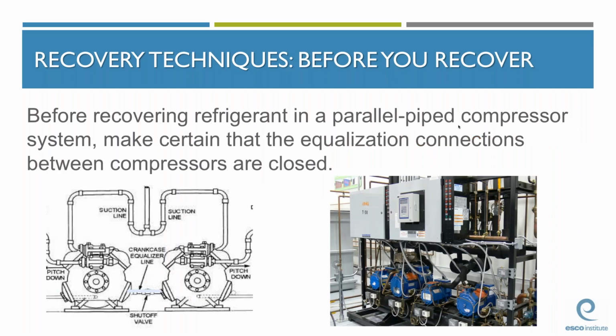Before recovering refrigerant from a parallel pipe compressor system or rack system, we need to make certain that the equalization connections between the compressors are closed. If these equalization lines are left open, the recovery process time will be affected. In addition, and probably more important than that, if these equalizer line connections remain open, oil can be pulled from one compressor to another, putting other system compressors in danger of experiencing mechanical failure due to lack of lubrication. So it's important that these external equalizer lines be shut.